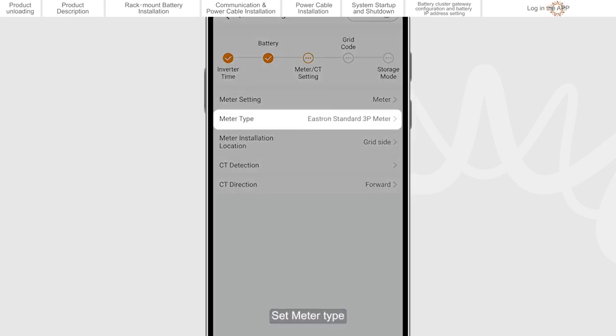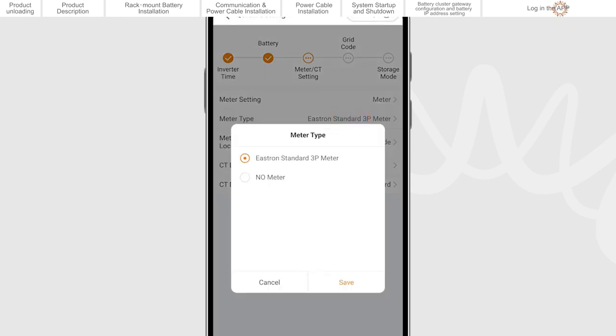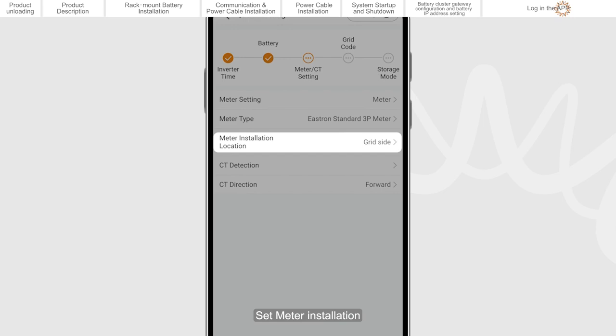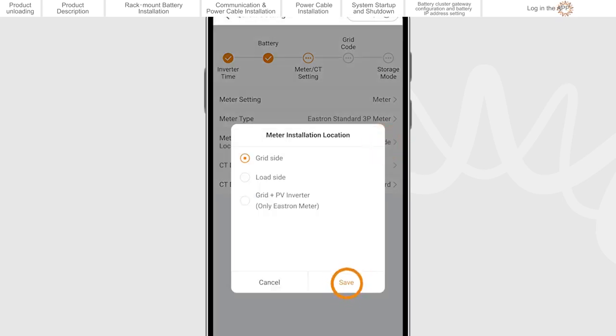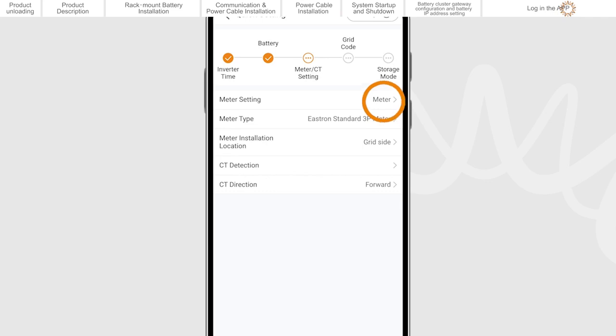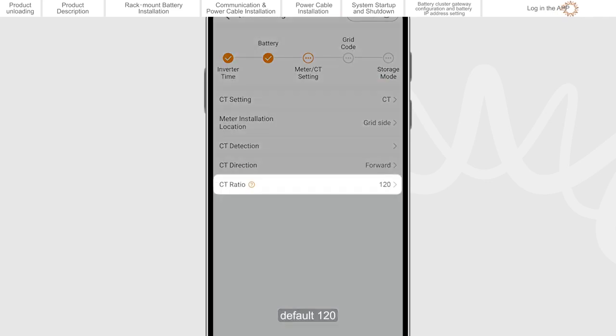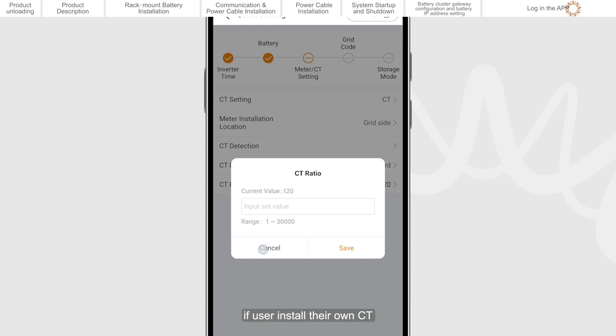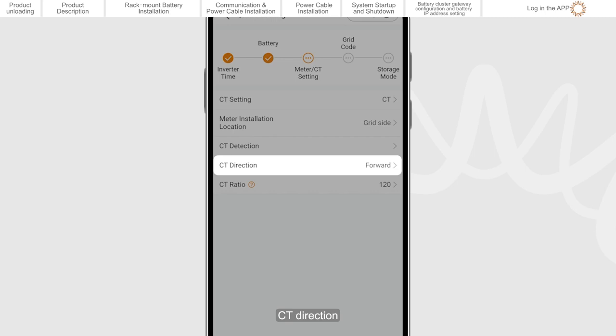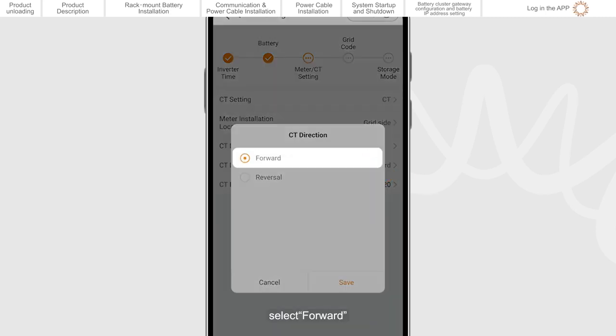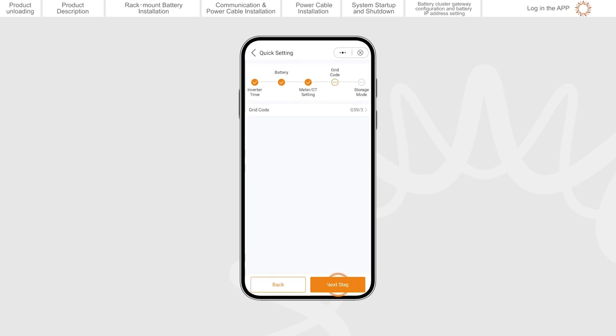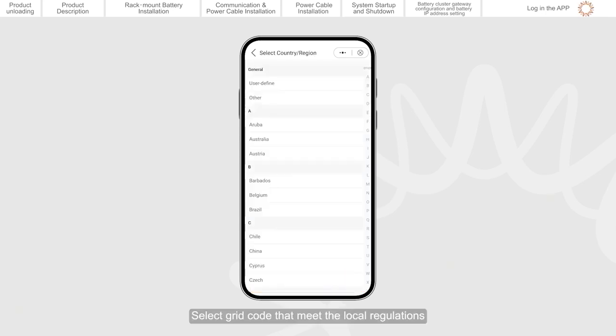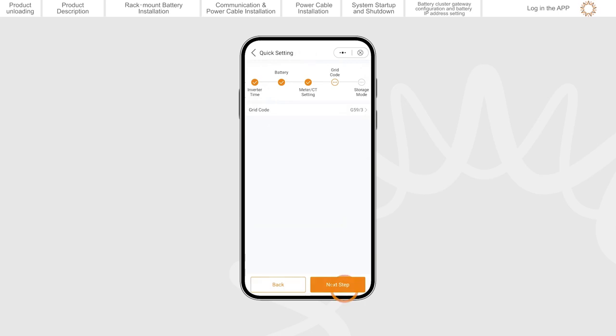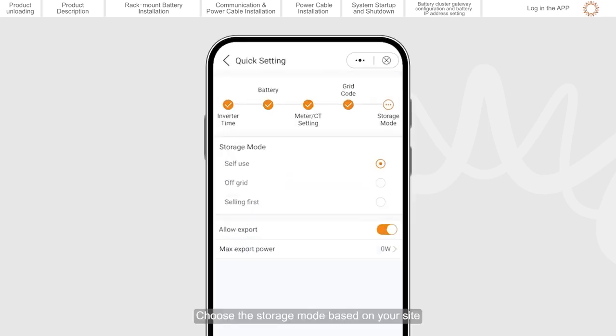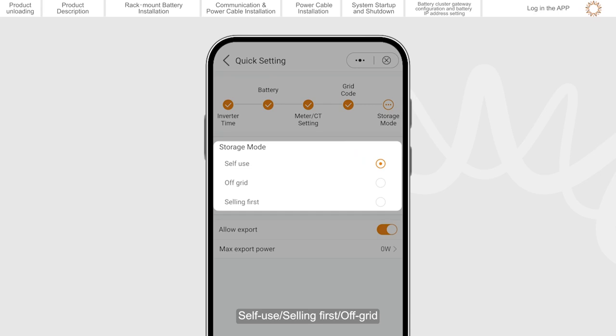Select meter. Set meter type. Set meter installation. Set CT ratio. Default 120. If user installed their own CT, they need to set CT ratio manually on app and meter. CT direction. Select forward. Select grid code that meet the local regulations. Choose the storage mode based on your site: self-use, selling first, off-grid.